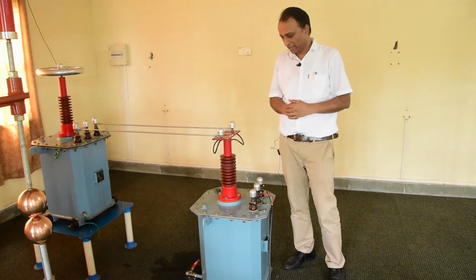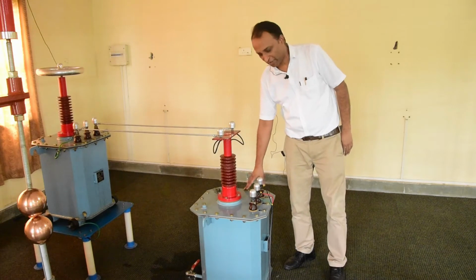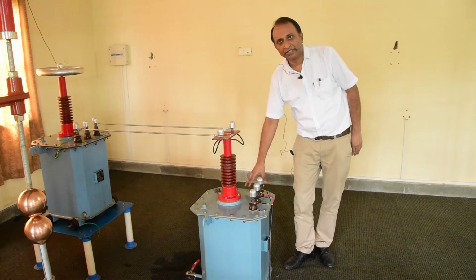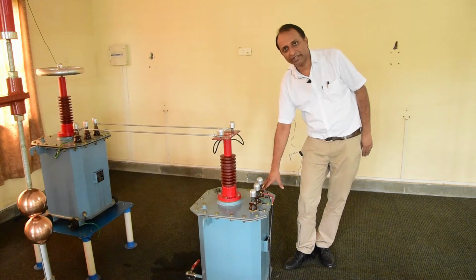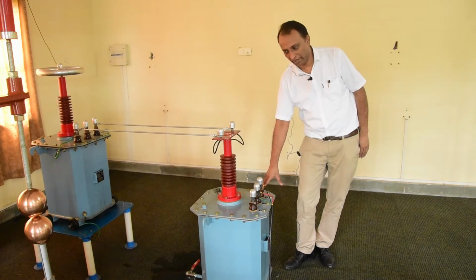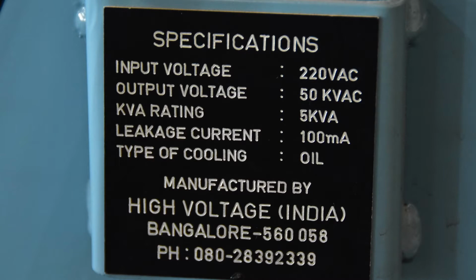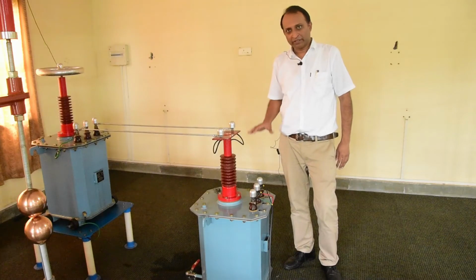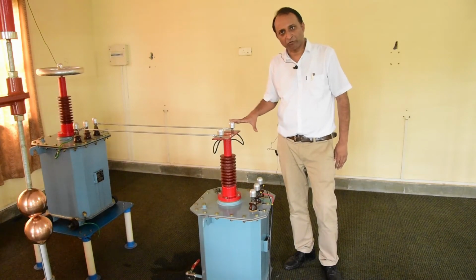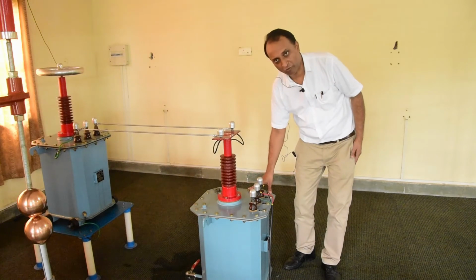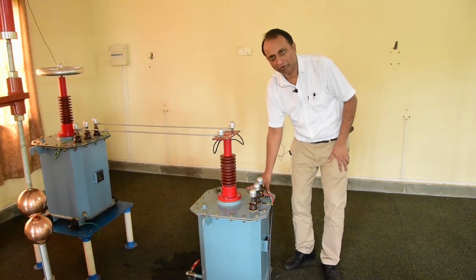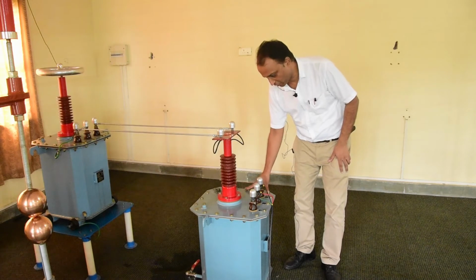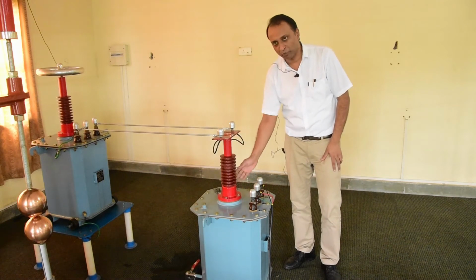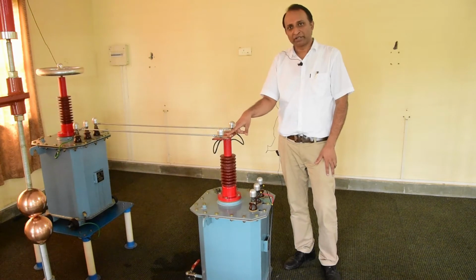That will be explained separately at a later stage. Please observe that this one is the first transformer. The transformer has an input voltage rating of 230 volts, and the output voltage it can provide, single phase, is 50 kilovolts, 50 kV. This is the first stage transformer. It's an oil filled type of transformer. The transformer is inside the tank, and this is a transformer bushing, and these are the terminals brought out.